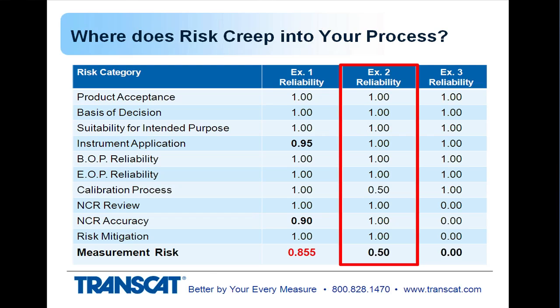In the next example, example 2, everything is good except for the calibration process where, for example, half of the test points were checked based on where the instrument is being used and how it's being used in the process. So if you didn't check all of the functions or all of the ranges of an instrument where it's being used, you've lost traceability in your measurement. You have no idea about the confidence of your measurement. So let's say half of those are being checked, you give that a value of 50%. Overall it drops to 50%.